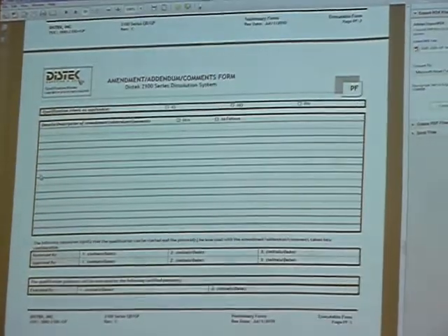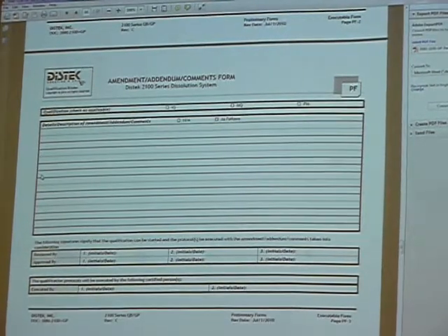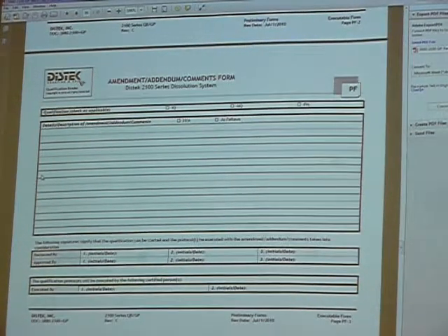We've had some customers that wanted extra temperature mapping done. Like we typically do all our testing at 37 degrees. There was one company, like I said, I brought that 40 degrees up because they wanted to run it at 40 degrees. They wanted to make sure that it was working right. So we simply wrote down that on page blah, blah, blah, the temperature test of 37 and 40 will be measured, 40 degrees will be written down here, or it might have been a separate page. We wrote down the temperature, or what the result was.